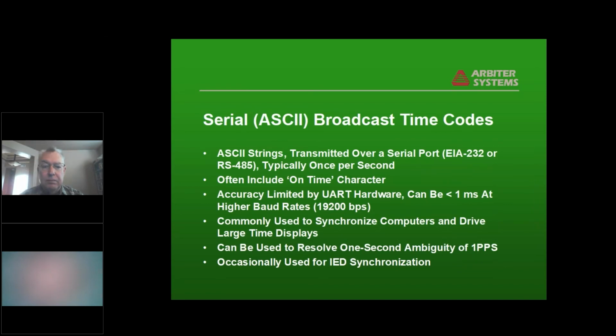We also have serial time codes that are basically data broadcast, typically in ASCII strings over a serial port, RS-232 or 485, typically once a second. They often have an on-time character that happens as soon after the top of second as the hardware can generate it. With higher baud rates, you can get this down to less than a millisecond with care in generation, and you also have to be careful in how you decode it. As I mentioned earlier, it's commonly used to synchronize computers and time displays that a millisecond is good enough for. It can also be used to resolve the 1-second ambiguity of 1 PPS.